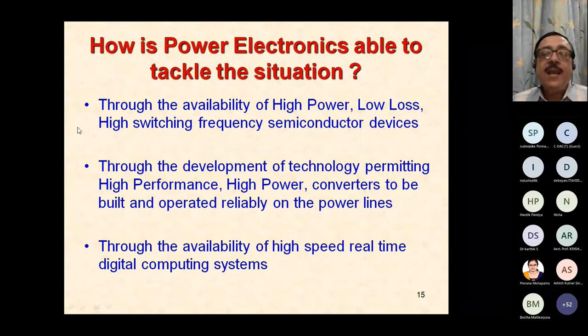And in real life, the conventional IGBT is silicon based, and we switch it, internationally, not only in this country, at roughly about 10 kilohertz in air natural cooled operation, and we can switch it at about 15 kilohertz or higher in force cooled applications, irrespective of whatever is said in the textbook. Because if you run it at higher frequencies, your losses will be higher. That's the catch. So if you want your system to be really efficient, you can't switch it at very high frequencies. Unless, of course, you go in for soft switching. That's a different issue.